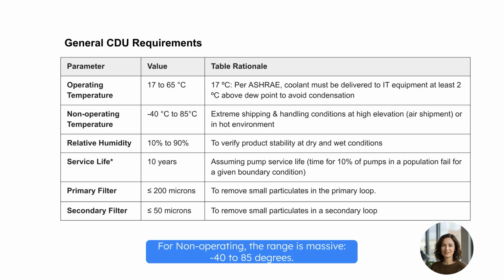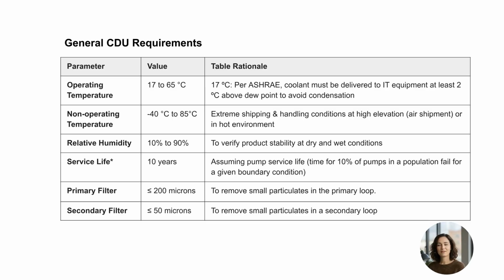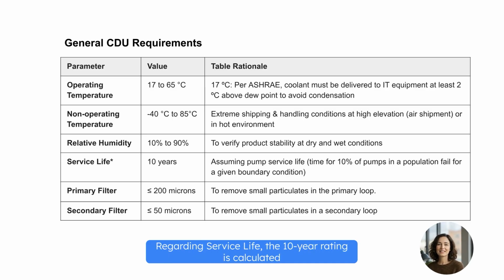For non-operating, the range is massive, -40 to 85 degrees. This isn't for the data hall. This is for logistics. It ensures the unit survives air shipment at high altitudes or storage in extreme heat. Regarding service life, the 10-year rating is calculated based on the pump's failure curve. Finally, check the filtration. We require a standard 200-micron filter for the primary loop, but a much finer 50-micron filter for the secondary loop. This is critical to prevent clogging in the microchannels. So when designing the loop, keep that 17-degree floor and the 50-micron requirement top of mind.